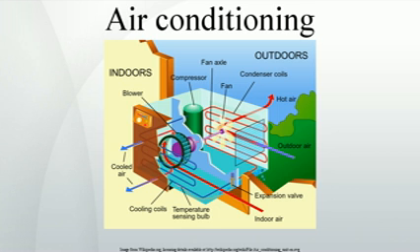Refrigerants. Modern refrigerants have been developed to be more environmentally safe than many of the early chlorofluorocarbon-based refrigerants used in the early and mid-20th century. These include HCFCs, R22, used in most homes today, and HFCs, R134, used in most cars, which have replaced most CFC use. HCFCs, in turn, are being phased out under the Montreal Protocol and replaced by hydrofluorocarbons, HFCs, such as R410A, which lack chlorine. Carbon dioxide, R744, is being rapidly adopted as a refrigerant in Europe and Japan.